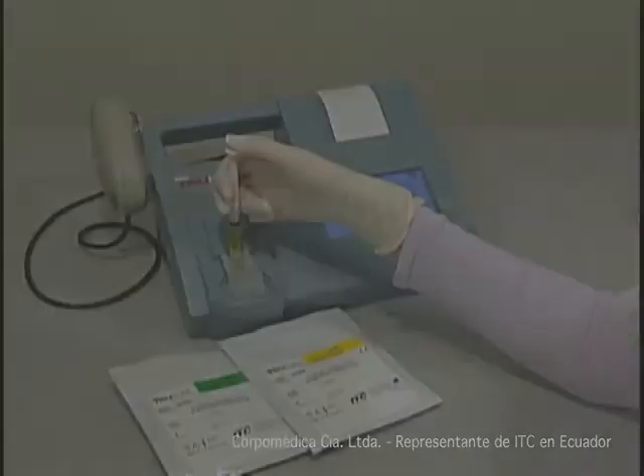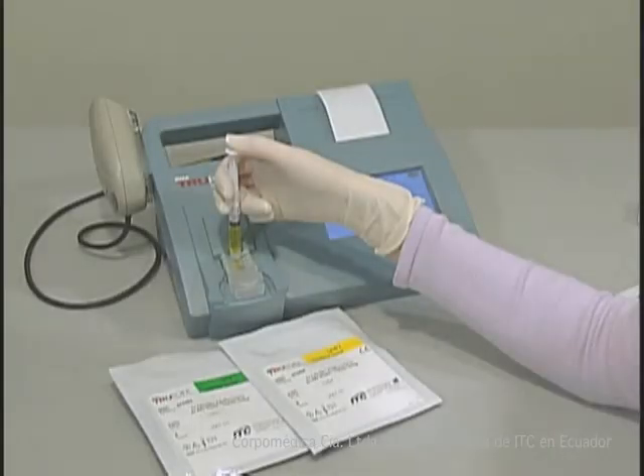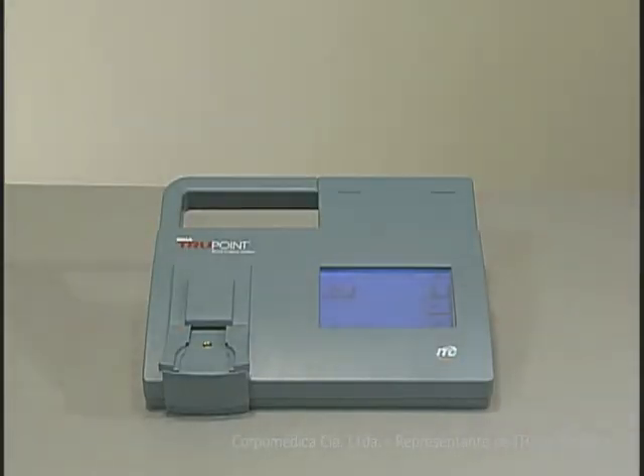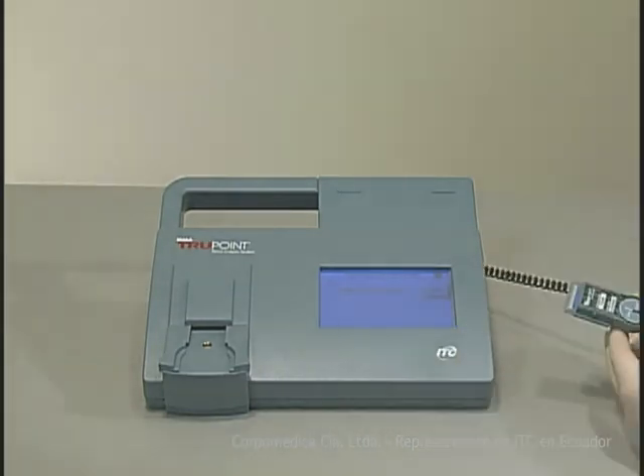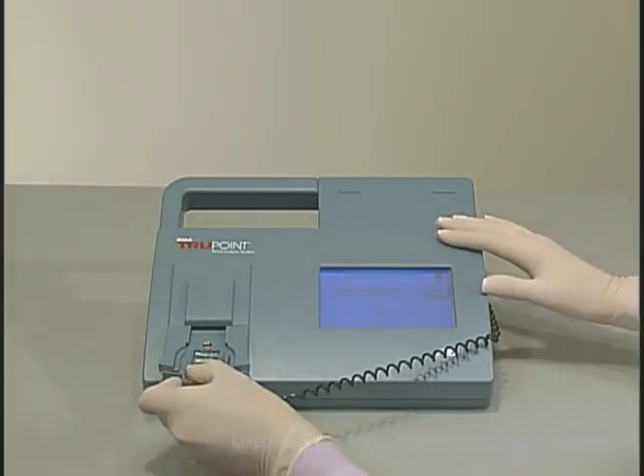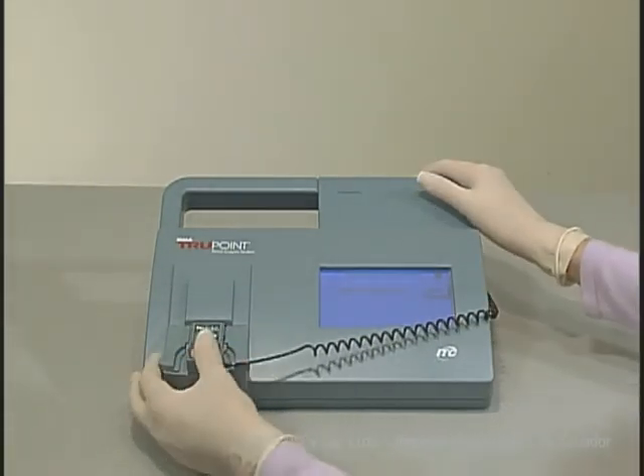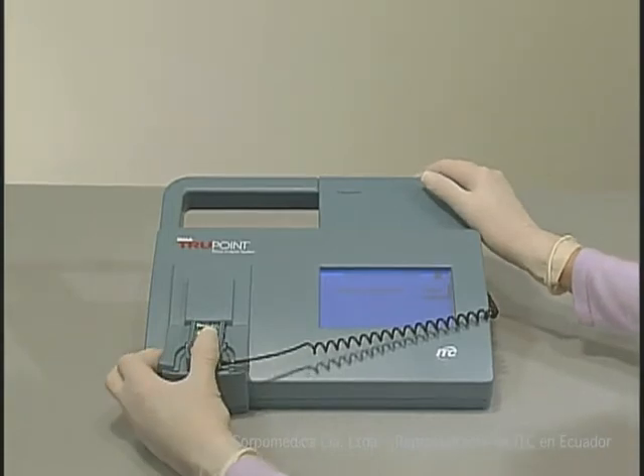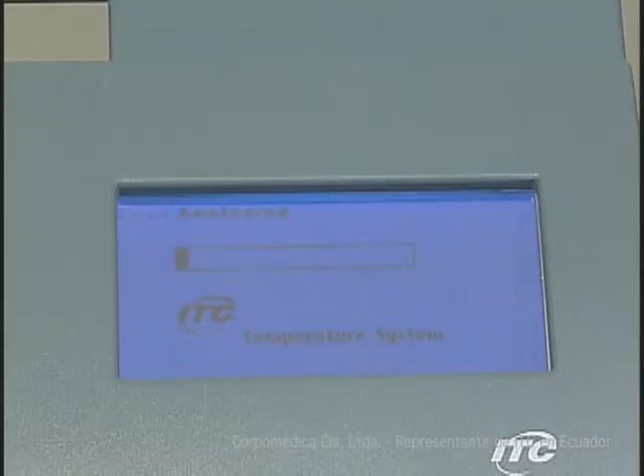For creatinine liquid quality control, use pre-filled control syringes that are available from ITC. To initiate a temperature test, press QC Test from the main menu. Press the thermometer icon on the QC Test Options menu. When instructed, insert the temperature card, which is located under the TruPoint, into the analyzer. Verify the temperature card serial number and cal code. A successful temperature test result will be displayed on the screen as passed.